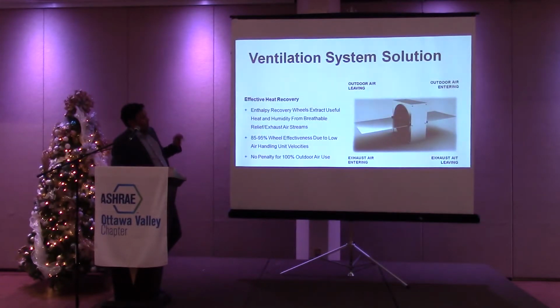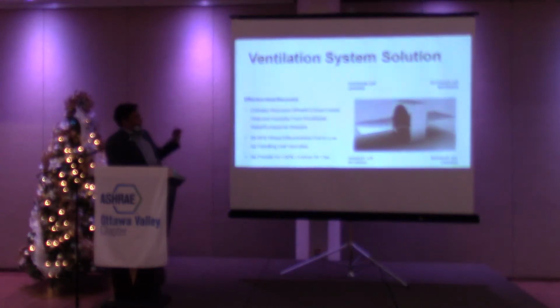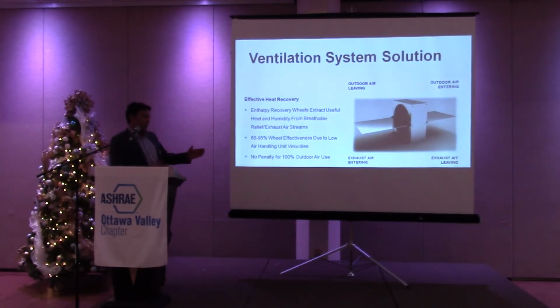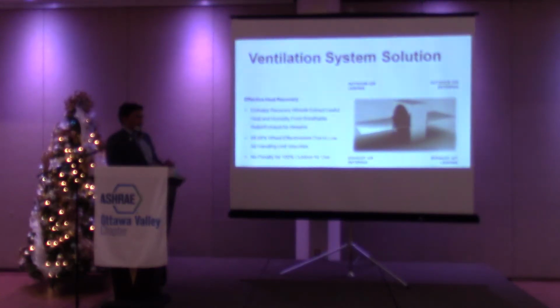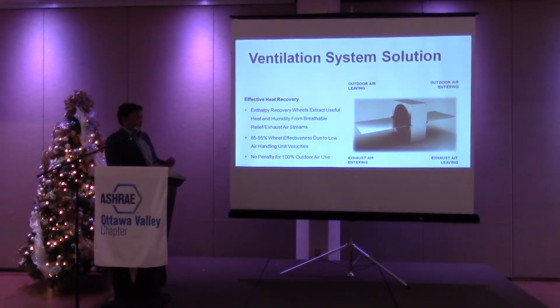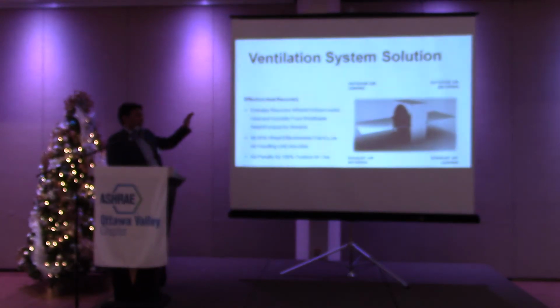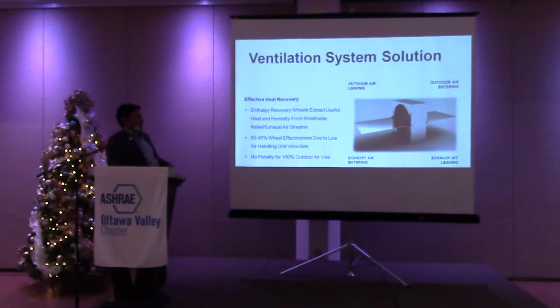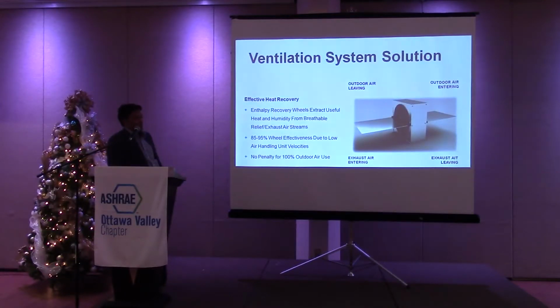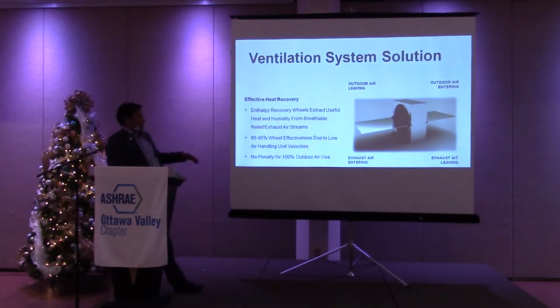So one of the aha moments we had on the project was when we were looking at the enthalpy recovery system, we had gone through and said, well, we know we need to recover heat. That's a given to meet the energy target. What we found was when we reduced the velocity of the air through the air handlers from 500 feet per minute to 300 feet per minute, or 250 feet per minute, depending on the air handler, we increased the effectiveness of the enthalpy recovery wheels. So you have more contact time, more transfer time with the wheels, and so we boosted and got 95% efficiencies in some of the wheels.